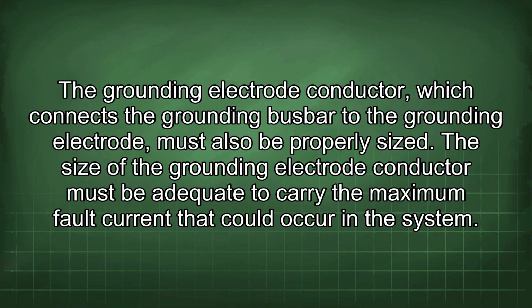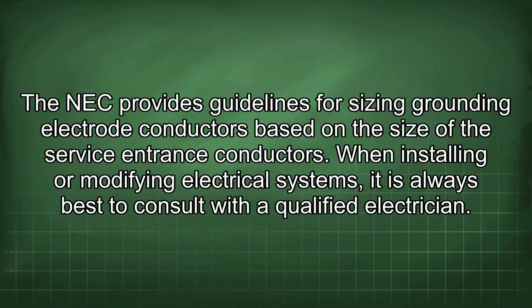The grounding electrode conductor, which connects the grounding busbar to the grounding electrode, must also be properly sized. The size of the grounding electrode conductor must be adequate to carry the maximum fault current that could occur in the system. The NEC provides guidelines for sizing grounding electrode conductors based on the size of the service entrance conductors.